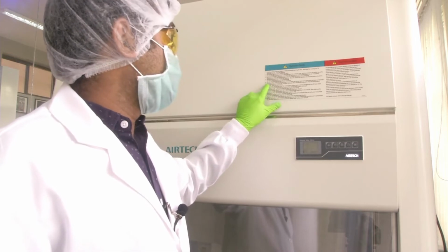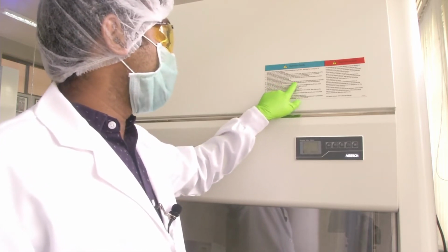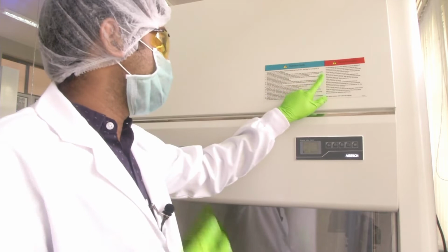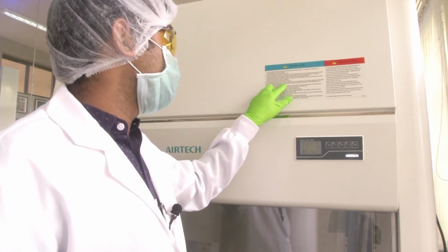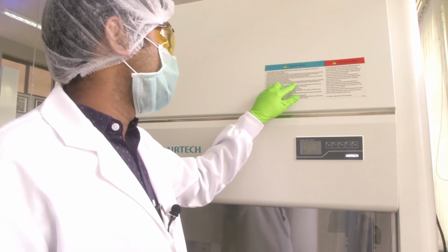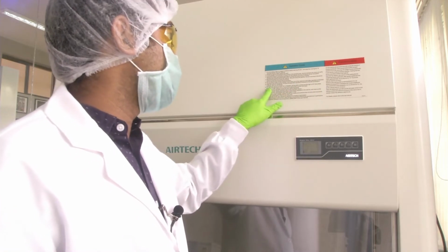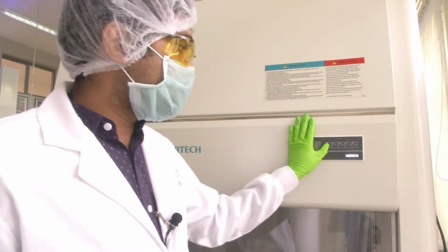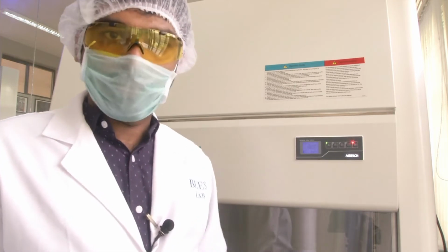Then, to ensure the safety of your articles, move them out of the cabinet in time after the operation is finished. Keep the cabinet running for 15 more minutes after the operation finishes for full self-purification, then turn off the fan. So the fan should run for at least 15 minutes.